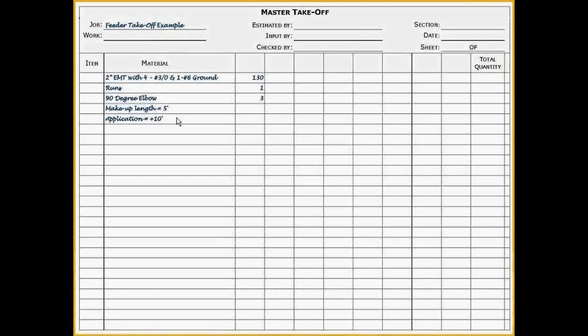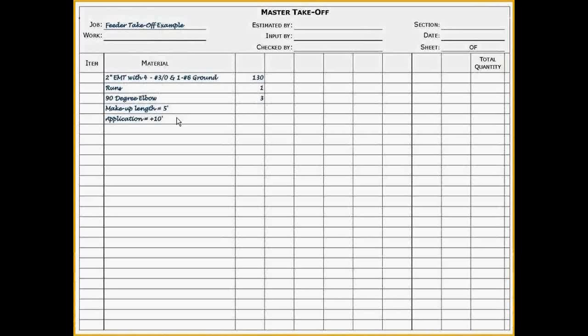A normal application refers to installation less than six feet off the floor with a flat working surface. In a concealed application, conduit would be installed inside walls or above ceilings. In an exposed plus ten feet application, the conduit would be installed ten feet above the floor requiring a ladder or scaffold to install the conduit. In an exposed plus twenty feet application, the conduit would be installed twenty feet above the floor. A man lift or scaffold would be needed to install the conduit. In a slab application, conduit would be installed around concrete forms and rebar. In an underground application, conduit would be installed in a trench.